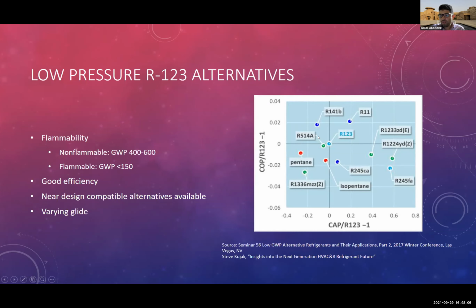So you can see that with R514, you have a slight reduction in COP and a slight reduction in capacity, and this can be corrected using some engineering application. For 1233ZD, you have significantly higher capacity and slightly lower COP, like 1% lower COP. And again, this can be corrected using proper engineering. Of course, 1233 is of a very low GWP. So this is going to be a good option if we can match the same efficiency.